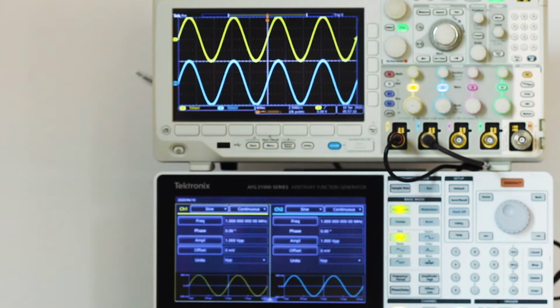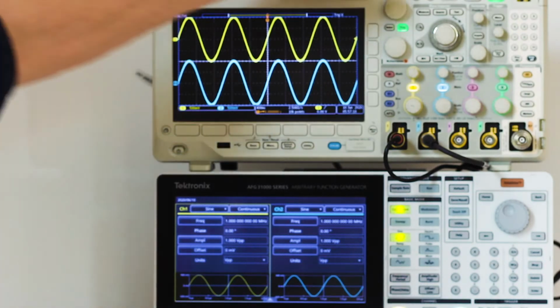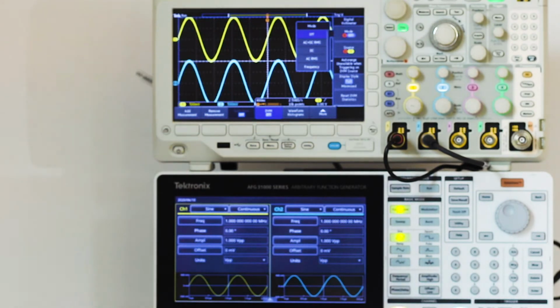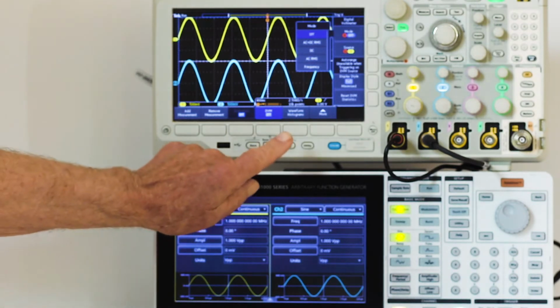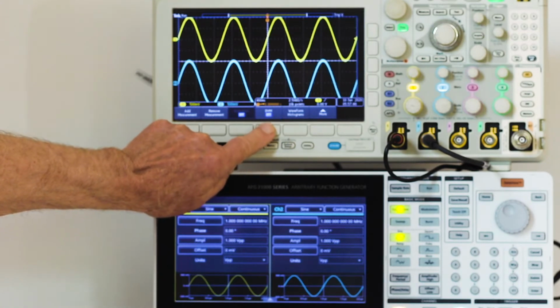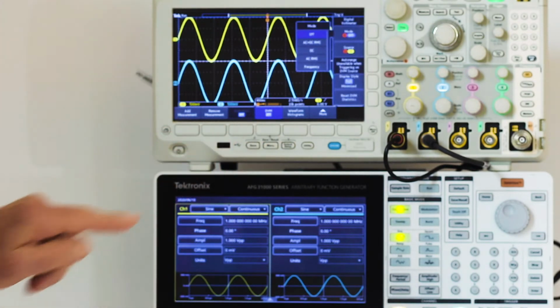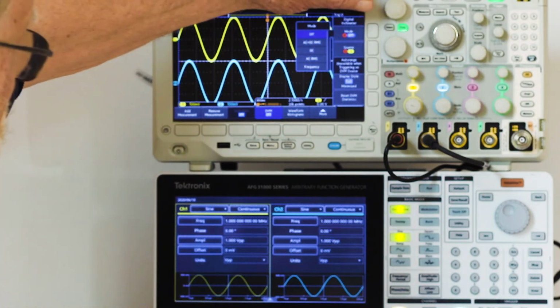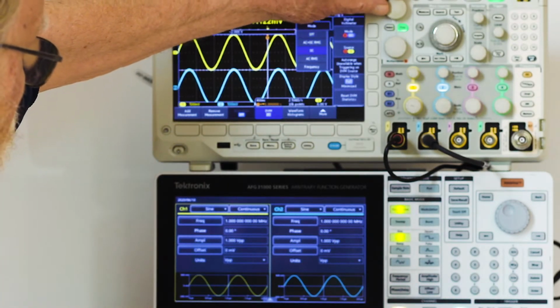A basic function in the oscilloscope is enabled by pressing the button labeled Measure. The fourth item in the horizontal Measure menu is DVM, Digital Voltmeter. Pressing the associated soft key, the vertical DVM menu comes up, and we can turn multipurpose knob A to see AC plus DC RMS, DC, AC RMS, and frequency.